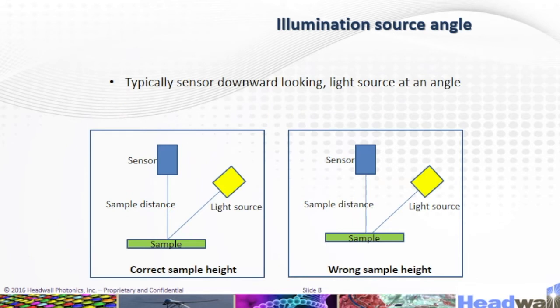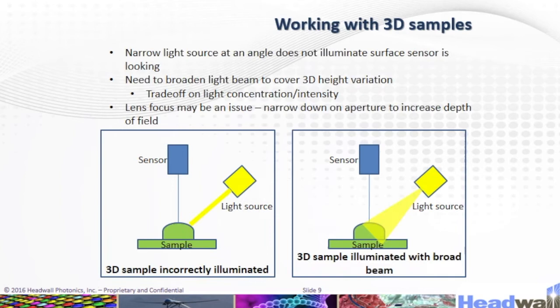Here we have the illumination source angle. Typically the sensor is downward looking with the light source at an angle. The diagram on the left-hand side shows the correct sample height, while the right-hand side shows the wrong sample height. When working with 3D samples, a narrow light source at an angle may not illuminate the surface the sensor is looking at. You need to broaden the light beam to cover 3D height variation, though this is a trade-off on light concentration and intensity. Lens focus may be an issue; narrow down the aperture to increase depth of field.